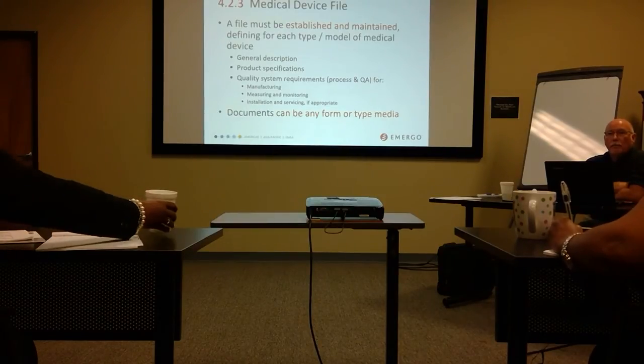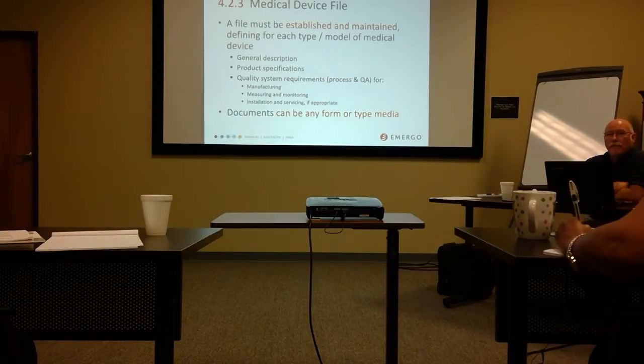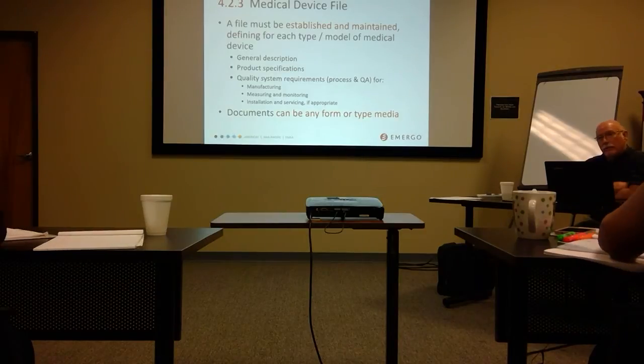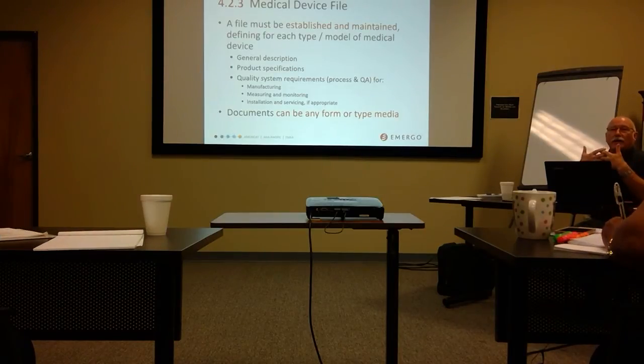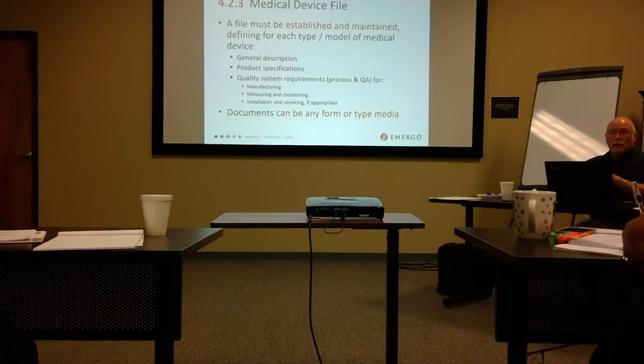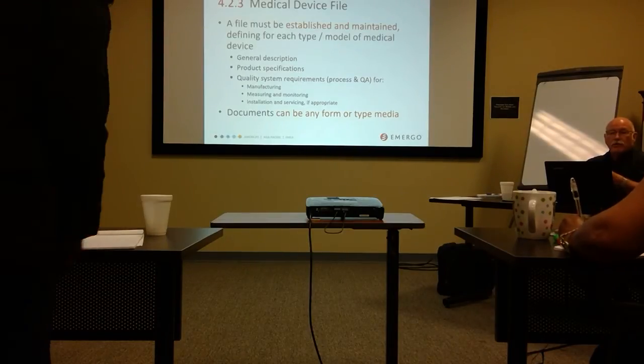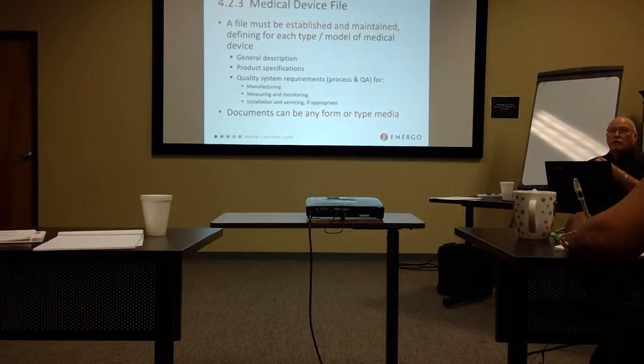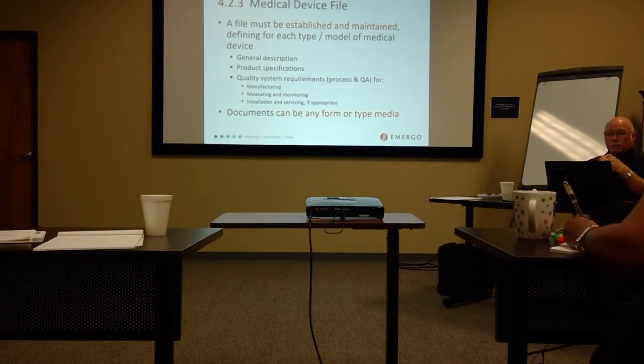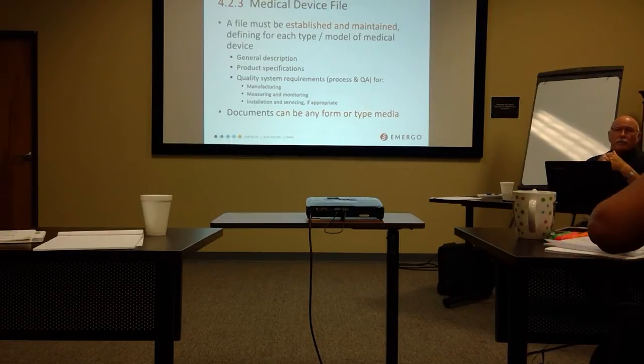So is this equivalent, I mean, from a structure and content standpoint, equivalent to the FDA? Very similar. There are a couple of very minor differences between the medical device file and the DMR. I would say 95% of the content is the same. There are a couple of European specific differences in the medical device file. At your option, you should already have a procedure that says this is how we do our medical device file, DMR. At your option, you could incorporate this into that procedure, or you can make it standalone, makes no difference. I do it both ways.